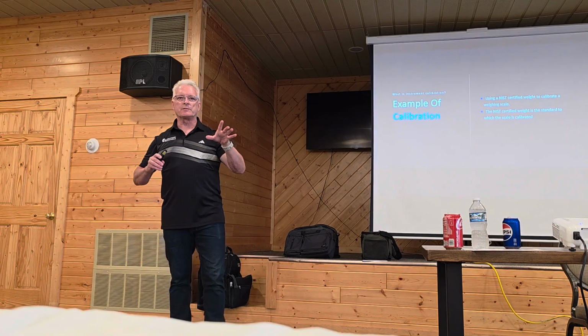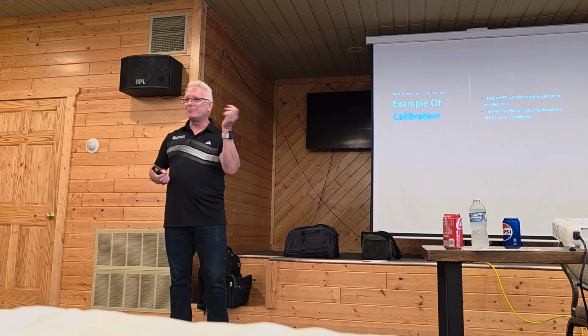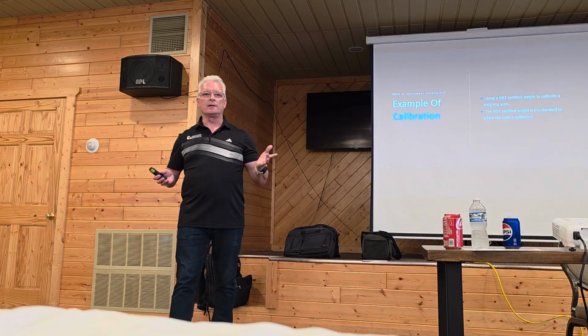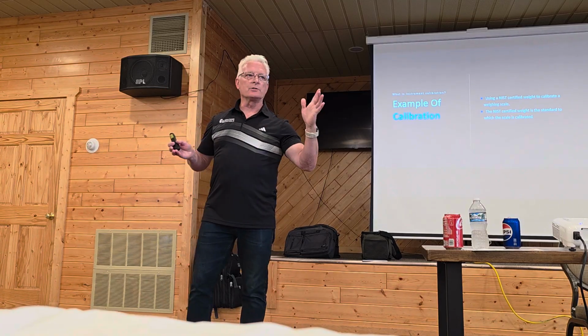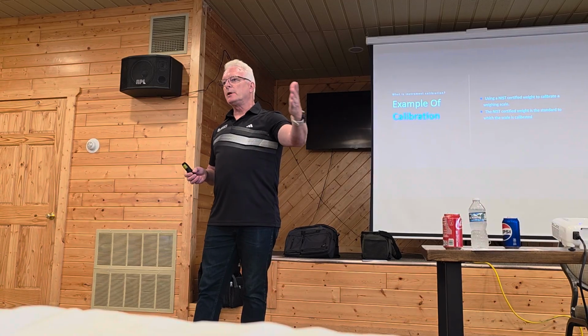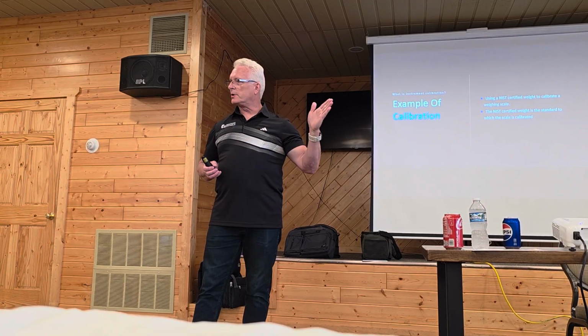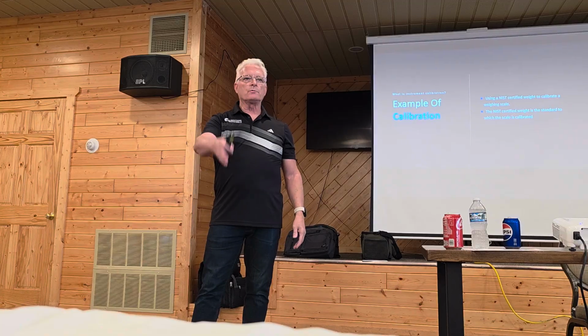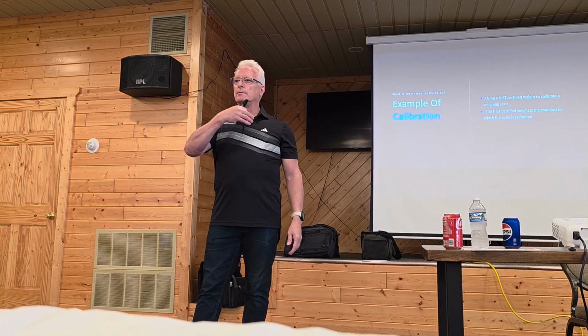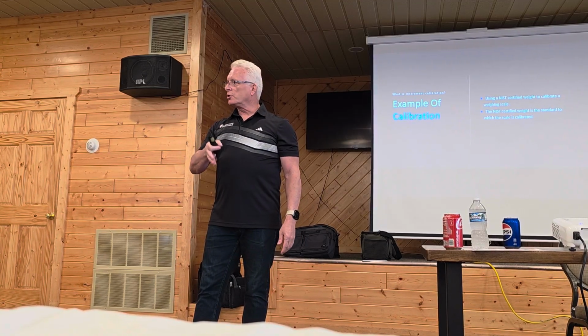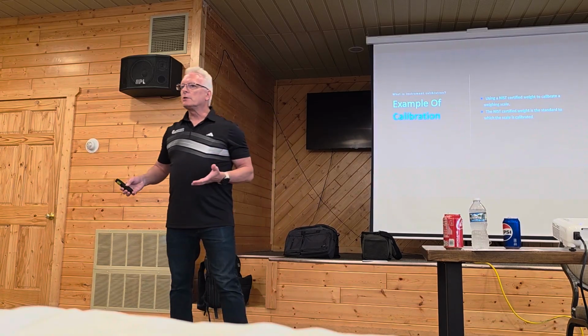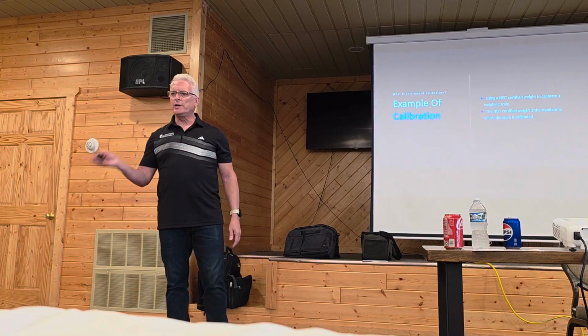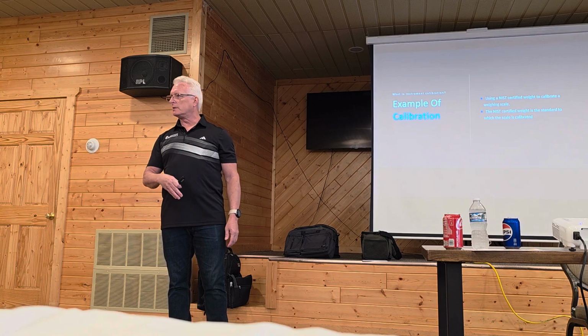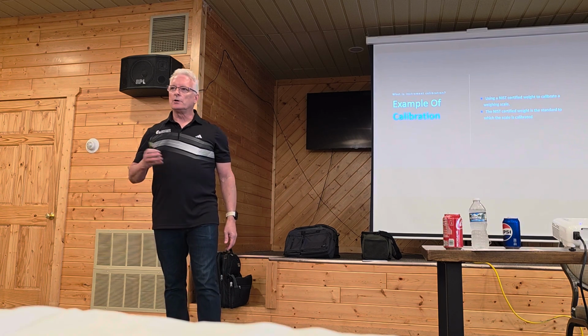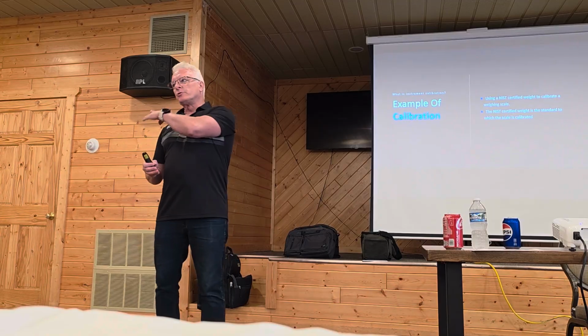So the mag meter companies have come out with a verificator, because they didn't want to fight that thing. So they call it a verificator. And every brand has a different one, different models. So we hook that up and it makes sure that that meter is exactly like it was when it was first built. So if it was installed right and all set up right and programmed right, it's still good. So it's still considered calibrated. The other way you can do it is with a clamp on if there's not a verificator available. So, and that's my 3rd choice.